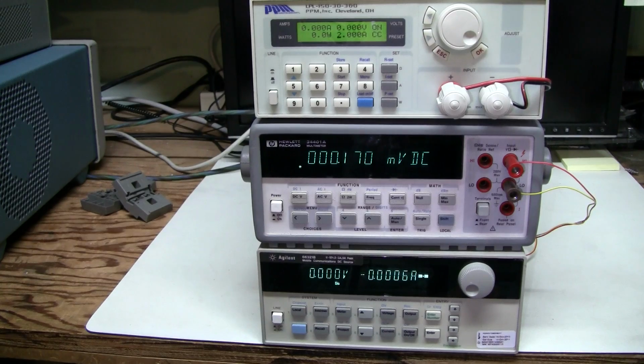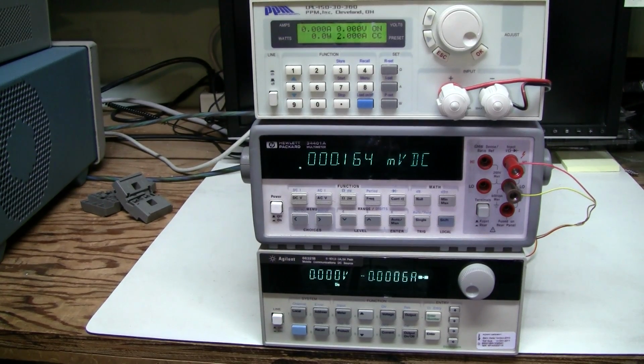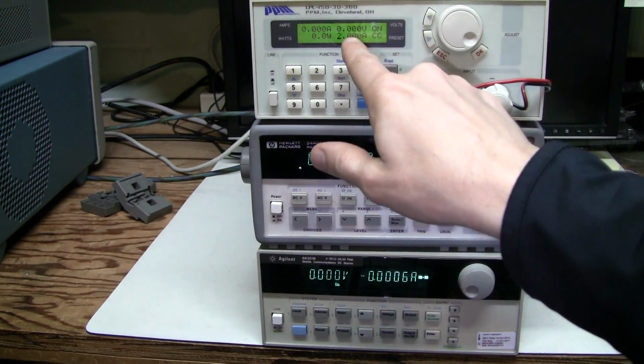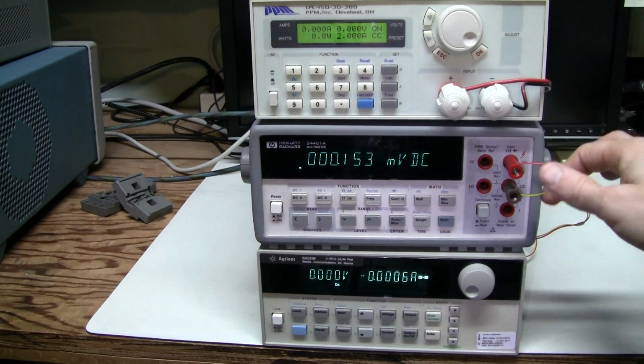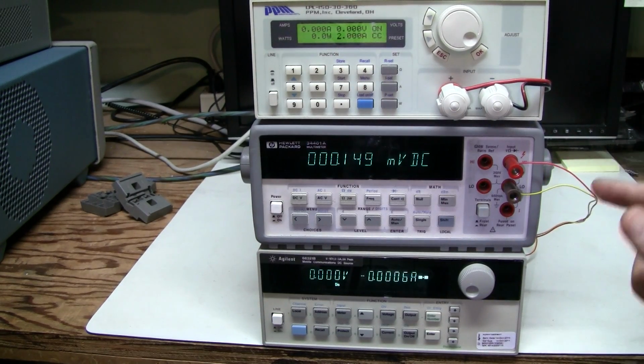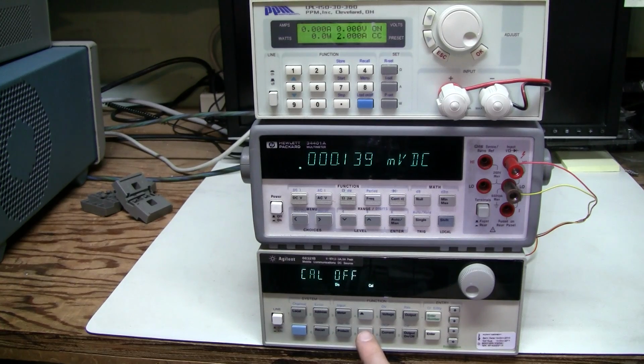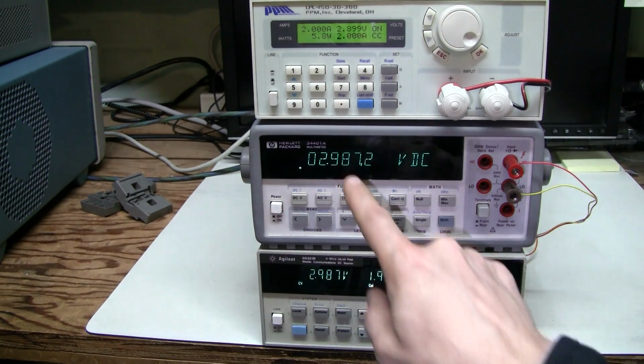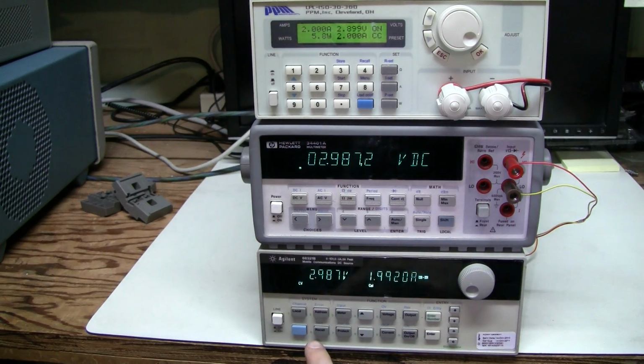And now one more step to calibrate the resistance. We need to set the electronic load to 2 amps, which I did. We are sensing the voltage on the back. And let's go to the calibration mode and select the resistance. Here it is. And now we need to go through 3 calibration points. Point 1, and we need to enter this voltage, which is very close.